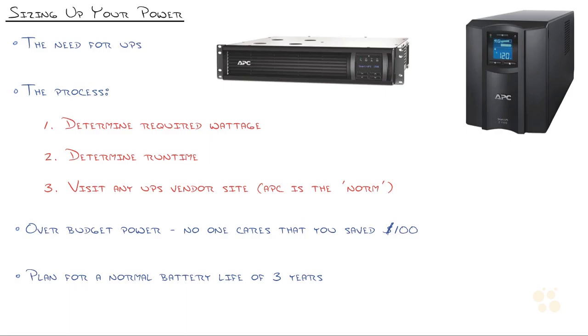Last thoughts on the UPS: first off, over-budget power. No one cares that you saved $100. A lot of times we as IT people want to save the company money and go for that short-term win - coming in saying it's only going to be $400 for a UPS when the last IT guy quoted $1,200. You look like a hero, until the power goes out and you get a 3-minute runtime because everything starts shutting down. The battery wasn't big enough.